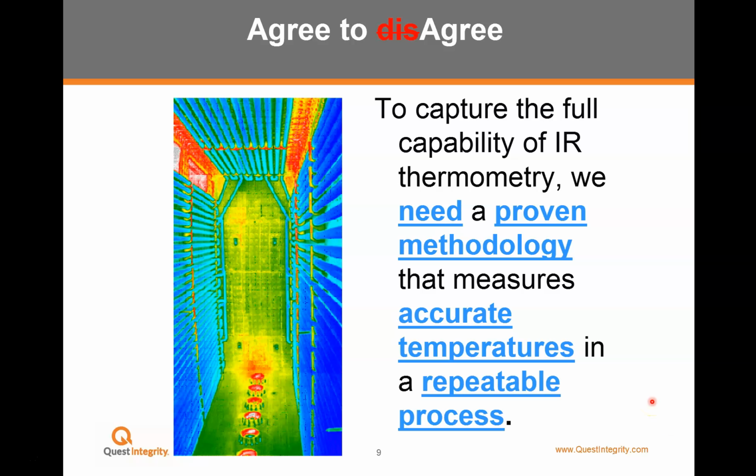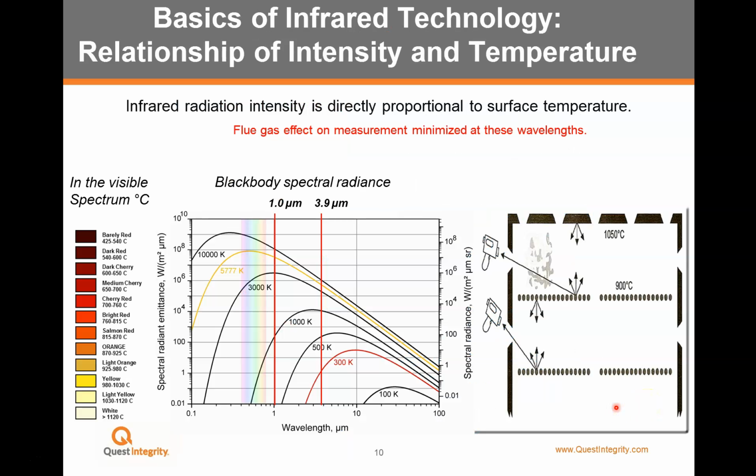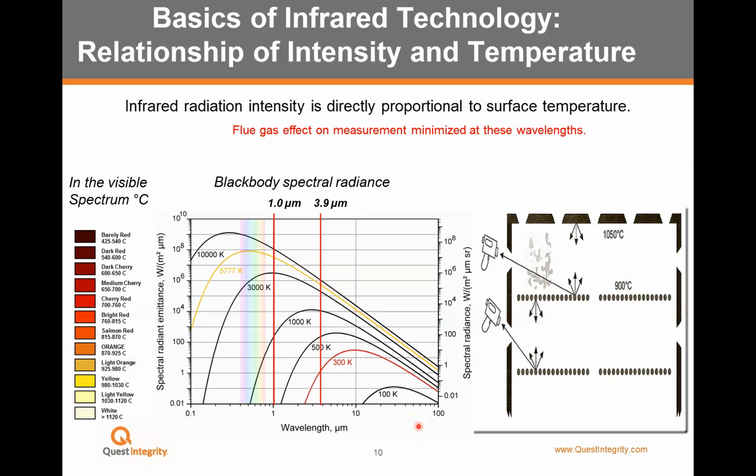And going back to basics is going to take us through the theory of how infrared works. Over here, what we see is what we call the black body spectrum, and all our cameras and instruments are calibrated to this black body. Now, this is just a theorized body, but what it tells us is these are the colors we can see with our naked eyes, and infrared, which is anything past the color red, is what we see with these infrared instruments. Now, a big misconception is that infrared measures temperature, but it actually measures the radiation that is emitted from the tube.